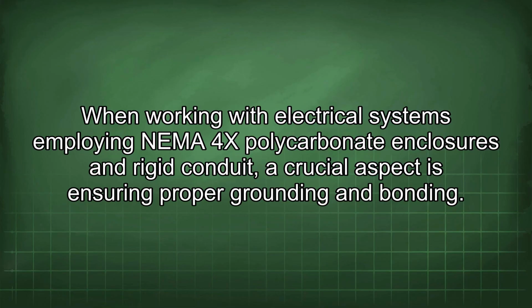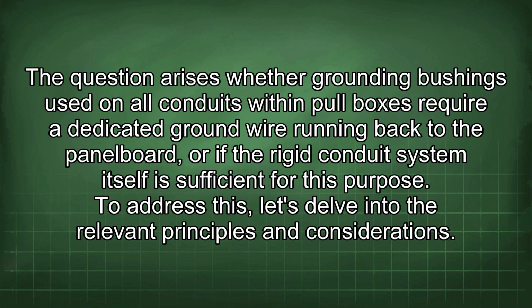When working with electrical systems employing NEMA 4X polycarbonate enclosures and rigid conduit, a crucial aspect is ensuring proper grounding and bonding. The question arises whether grounding bushings used on all conduits within pull boxes require a dedicated ground wire running back to the panel board, or if the rigid conduit system itself is sufficient for this purpose. To address this, let's delve into the relevant principles and considerations.